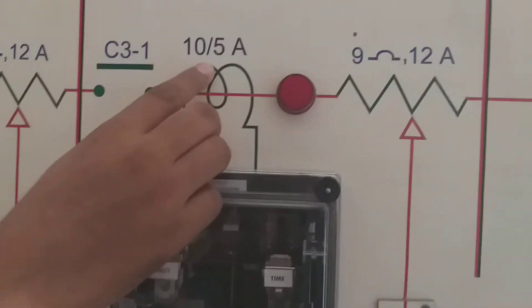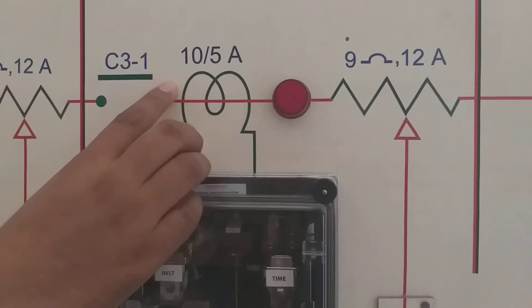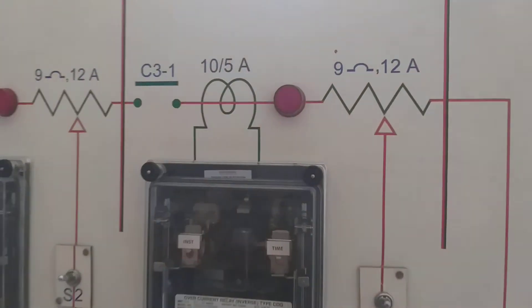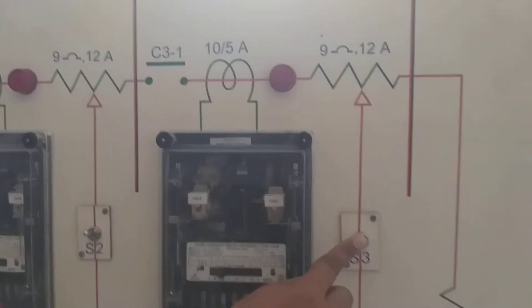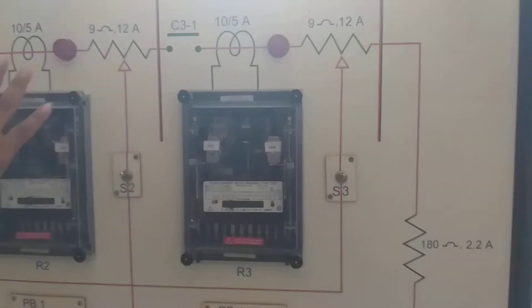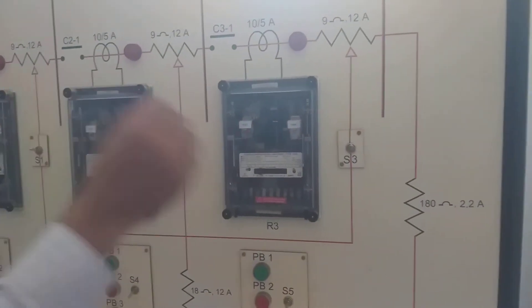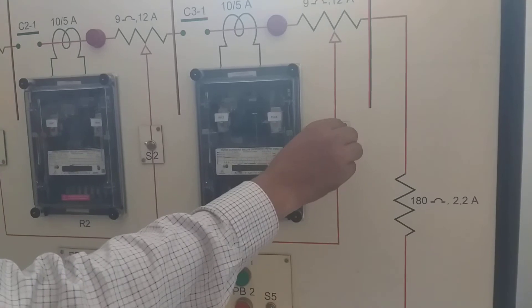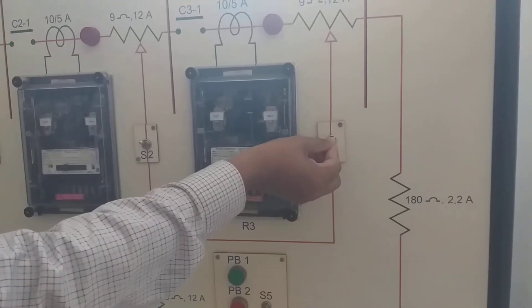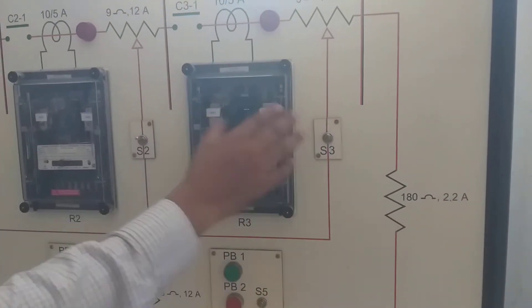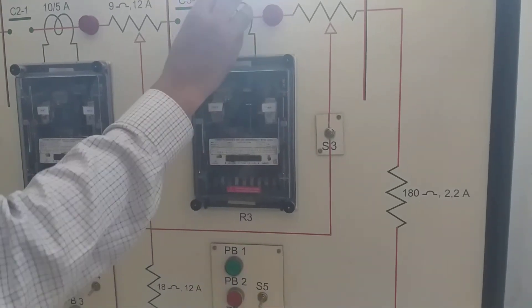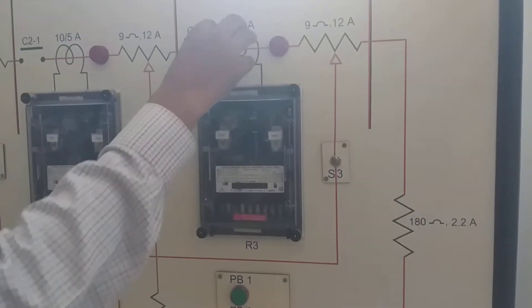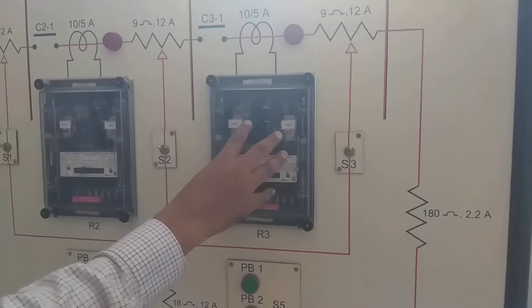The CT ratio is 10 by 5 amperes, meaning 10 amperes on the primary and 5 amperes on the secondary. These are the fault switches. Here the fault is not yet created, but when we apply the switches it means a fault is created in the circuit. The CT will then sense the fault current and give a signal to the relay.